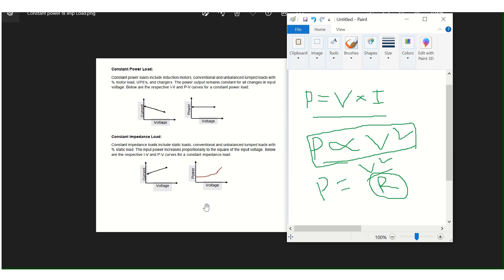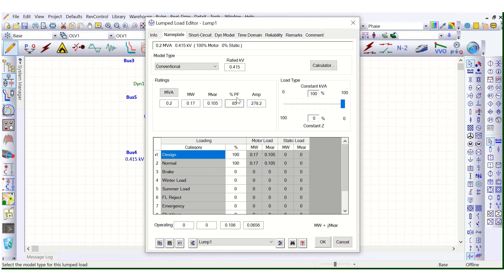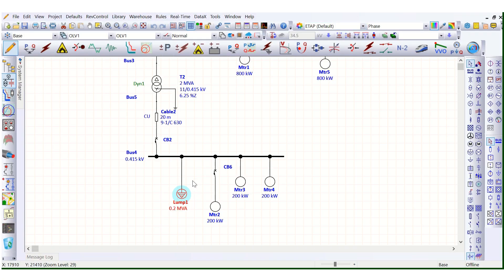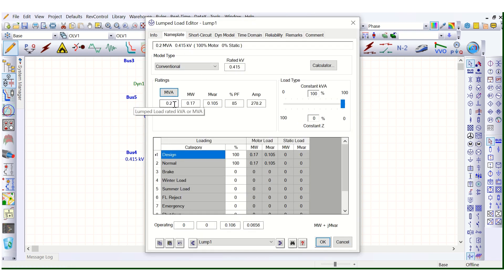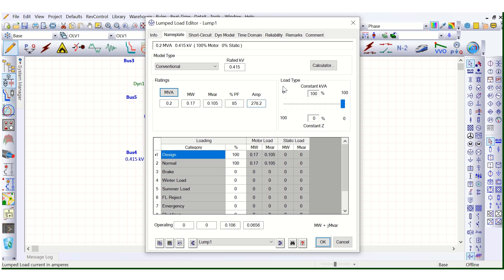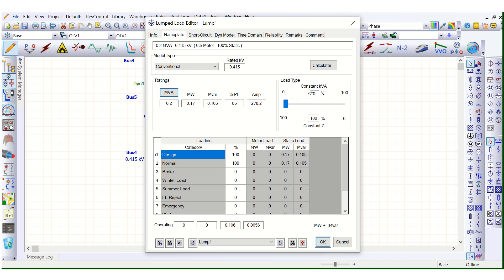Now let's validate this with ETAP software. We have selected this lump load — rated 0.2 MVA at 85% power factor. Here is the load type setting where you can see the percentage motor load and the percentage static load. The upper part represents constant KVA, meaning constant power load, and the bottom part represents constant impedance load.